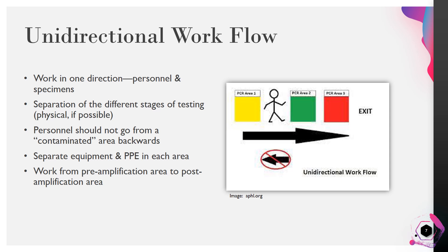Unidirectional workflow simply means to work in one direction. Testing personnel and specimens should flow in one direction without backtracking to previous areas. The workflow should go from preamplification or pre-PCR to postamplification or post-PCR. It is highly recommended to have separate equipment and PPE in each testing area, and to have physical separation between each area. This can look different depending on the lab space, testing volume, and budget.